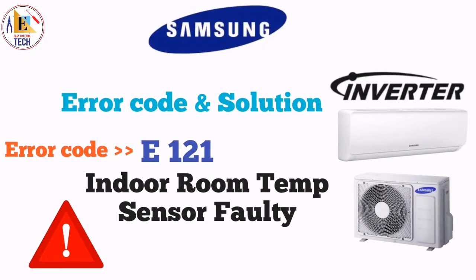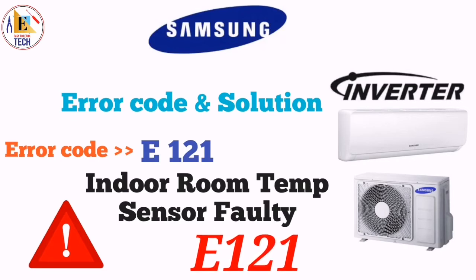When you see an error on your display E121, it means it's an indoor room temperature sensor error. And if your indoor unit has a 3 LED display, when the second LED is blinking and LED 1 and LED 3 are off, at that time also the indoor room temperature sensor is faulty. First of all, you have to check whether the indoor room temperature sensor is connected to the PCB perfectly or not, and whether the placement of the sensor is correctly done or not.